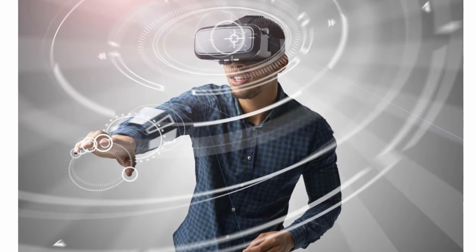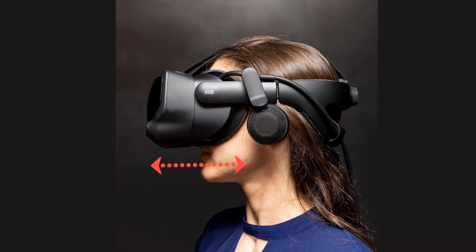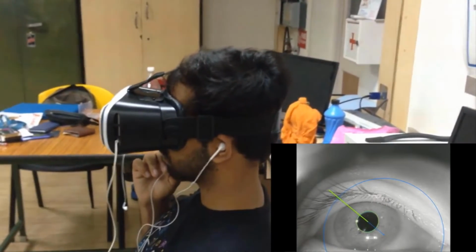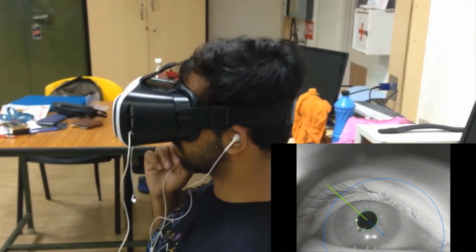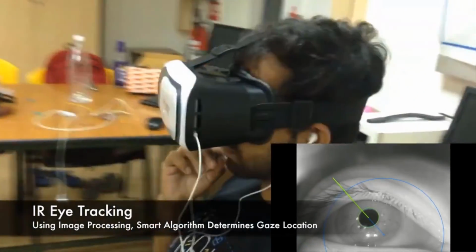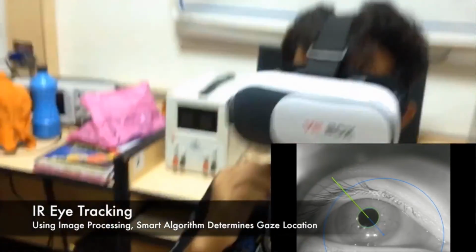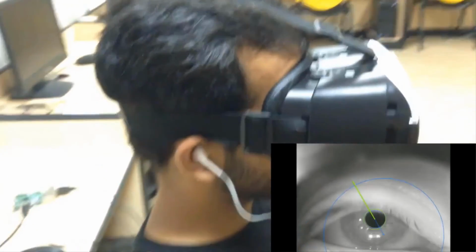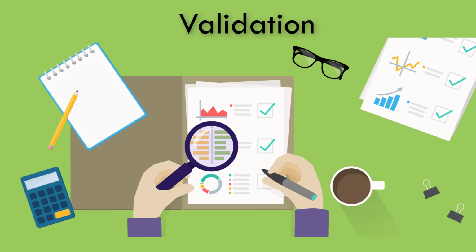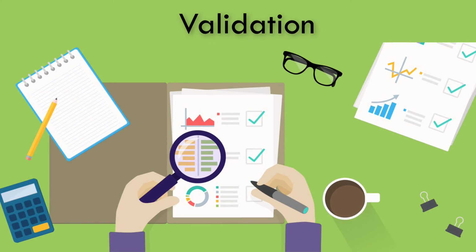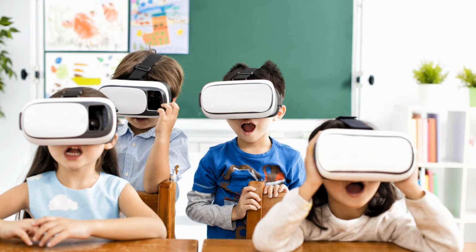Major limitations of portable devices are inability to control fixation and distance from eye to screen. The current developments address these disadvantages by employing adjustable fixation using a gaze tracker. This compensates for the fixation deviations. That is, no matter where the patient is looking, the stimulus can be shown relative to fixation at that moment. The perimeters based on virtual reality of course need validation and development of a normative database. But the future looks bright for virtual reality-based field testing.